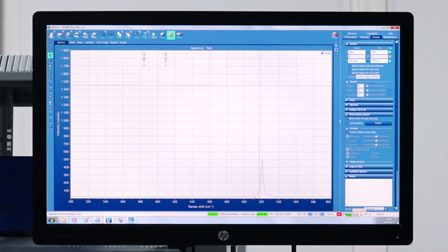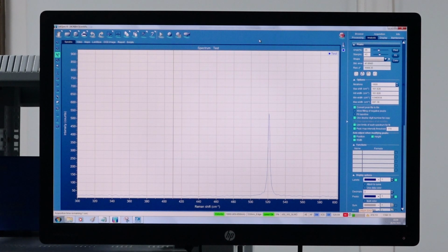In the real time display, I can change the focus and see how the real time display signal changes, because I have focused my sample using a yellow light, but I am making the acquisition using the green light. Therefore, a slight focusing will actually increase the Raman signal. Now as the RTD signal acquisition is going on, I will adjust the focus on the sample using the fine adjustment knob and see the changes in the display of the RTD signal.